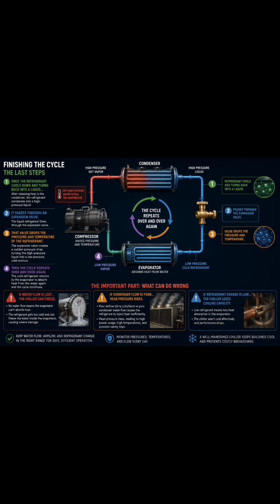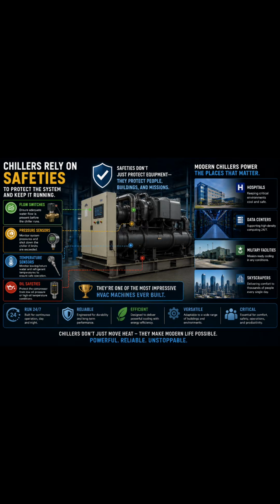Now here's the important part. If water flow is lost, the chiller can freeze. If condenser flow is poor, head pressure rises. And if refrigerant charge is low, the chiller loses cooling capacity. That's why chillers rely on safeties like flow switches, pressure sensors, temperature sensors, and oil safeties.